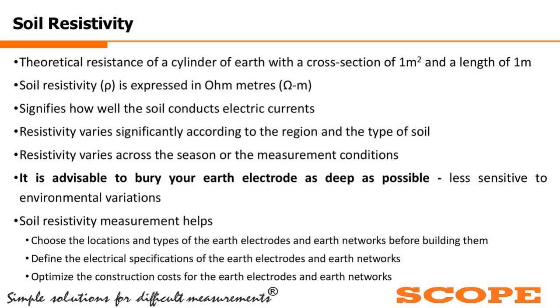To understand resistivity, we have to consider the theoretical resistance of a cylinder of earth with a cross section of 1 square meter and a length of 1 meter. Or, for visual identification, it is a solid pipe or earth rod of 1 square meter cross section and 1 meter length. What will be the resistance of that? That is called resistivity, because if the resistance of one unit is this much, we can work out how much the resistance will be over the surface.